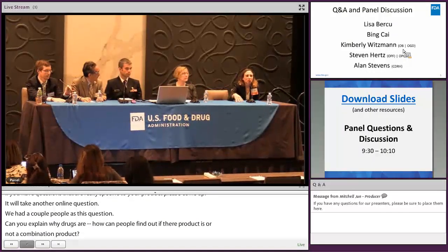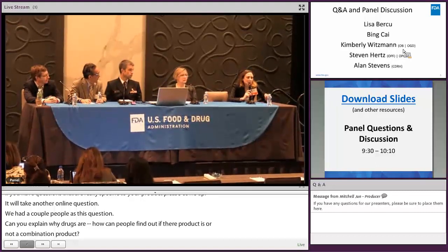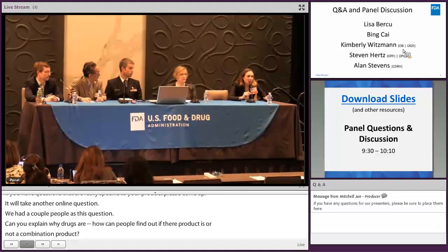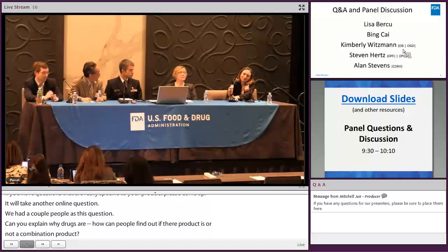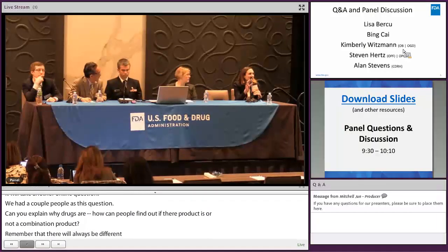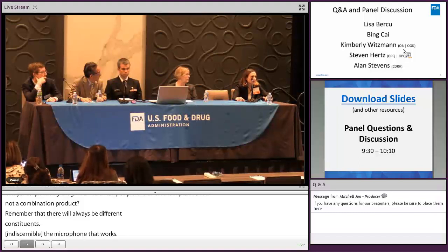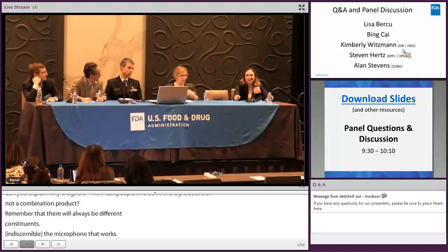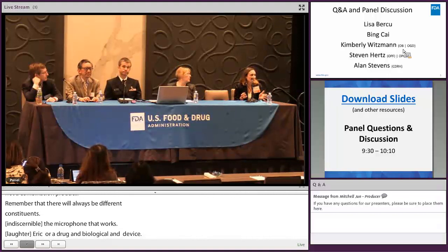If you want to know whether something is a combination product, remember that there are always going to be two different constituents. So you're going to have either a drug and a device constituent, or a drug and biologic, or a drug, biologic, and device. If you have specific questions, you can submit an RFD, which I mentioned in my presentation, or a pre-RFD to the Office of Combination Products. That's the office within FDA that has the jurisdiction for determining whether something is or is not a combination product.